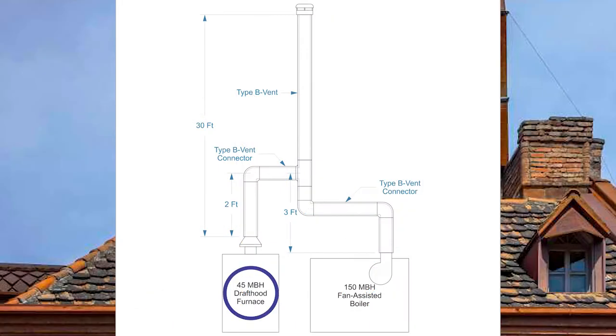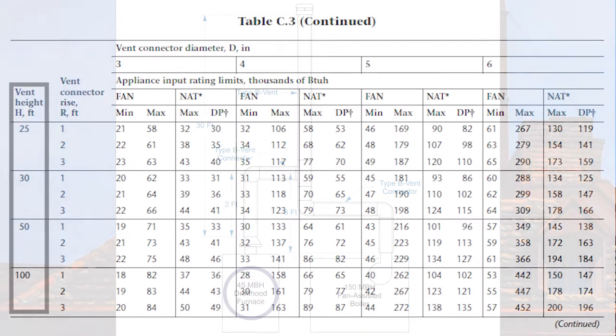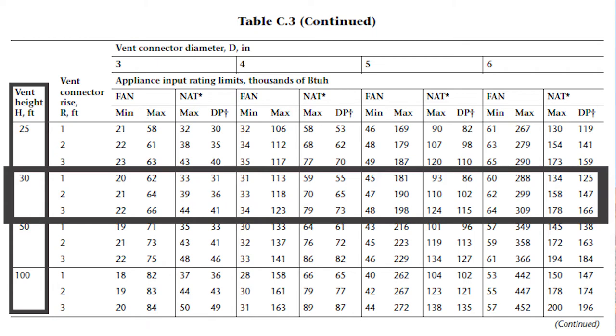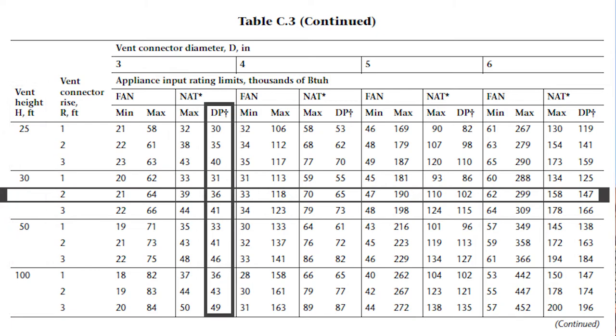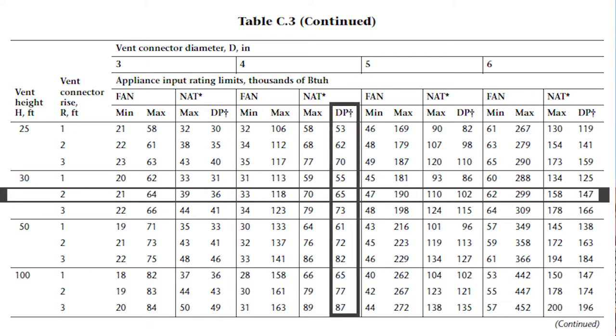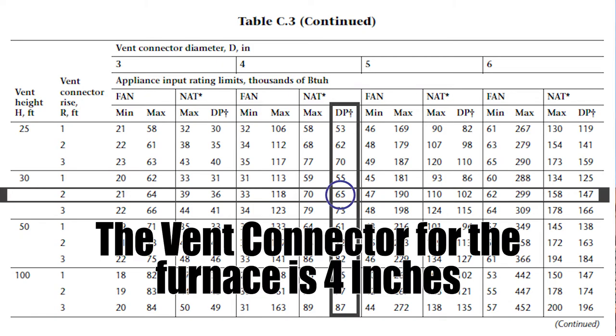Let's look at the draft hood equipped furnace first. Coming down to the 30-foot vent height, across on a two-foot vent connector rise, going to NAT DP. The three-inch vent connector for NAT DP is 36,000 BTUs — not quite enough. Over to four inch is 65,000 BTUs. So I will have a four-inch vent connector for my furnace.